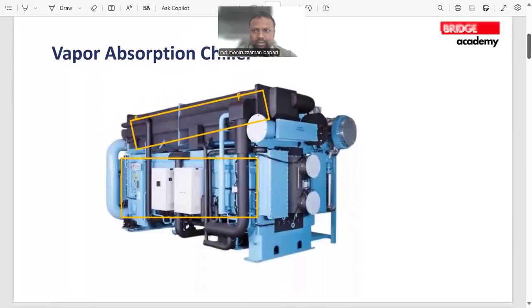First of all, let's check out its look. Vapor absorption chiller looks like this. There are actually two chambers. There is one chamber at the top and there is another chamber here at the bottom, and there are pipelines connecting the top chamber with the bottom chamber, and there are also some pipelines connecting from the chiller to outwards, like chilled water going out, coming in, or cooling water going out and coming in. Those sorts of pipelines are in here.